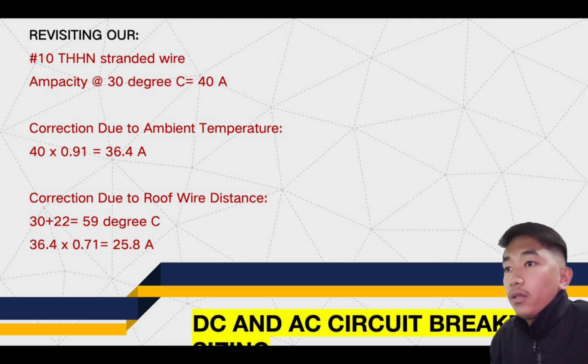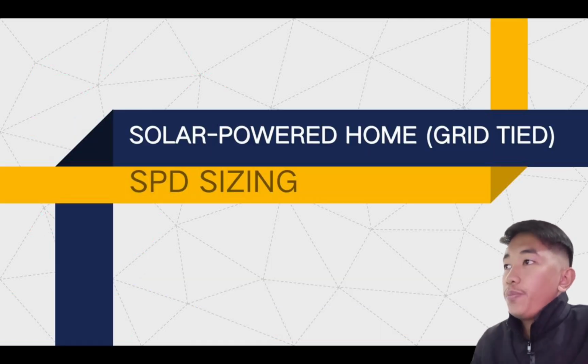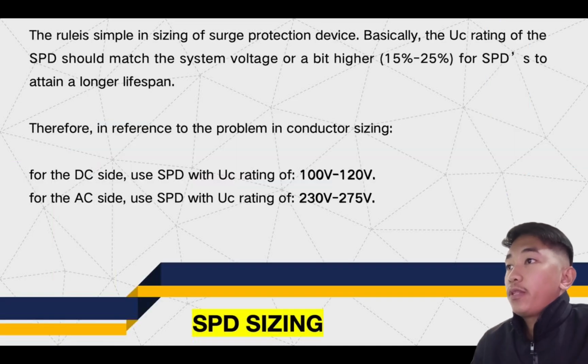So we get our final ampere for our number 10 THHN stranded wire. That is a 25.8 ampere. Next is SPD, or surge protection device. The rule is simple in sizing a surge protection device. Basically, the UC rating of the SPD should match the system voltage or be a bit higher, 15% to 25%, for SPDs to attain a longer lifespan.